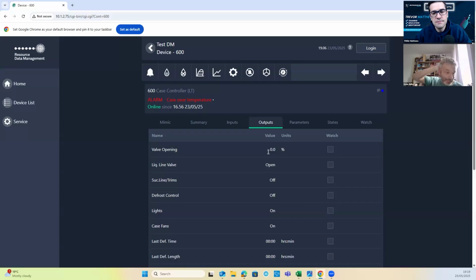Okay. So I'm listening to that. That's pulsing away. I'm happy. I'm then going to switch my fans on. And with a fair wind, the fans are going to start. And I'm going to be like, yes, I've got a chance of running this today, which is what we all want to do. I'm also going to be looking at my transducer, if I've got a transducer fitted. Now, what I'm going to bear in mind is if I'm on vacuum and it's not a -1 to something pressure, let's say 1,000 psi, 100 bar, whatever. If I'm in the vacuum and it's not rated to -1, I may be showing a fault. If it's a -1 to 65 bar transducer, I should be showing a reading on my transducer at this point.